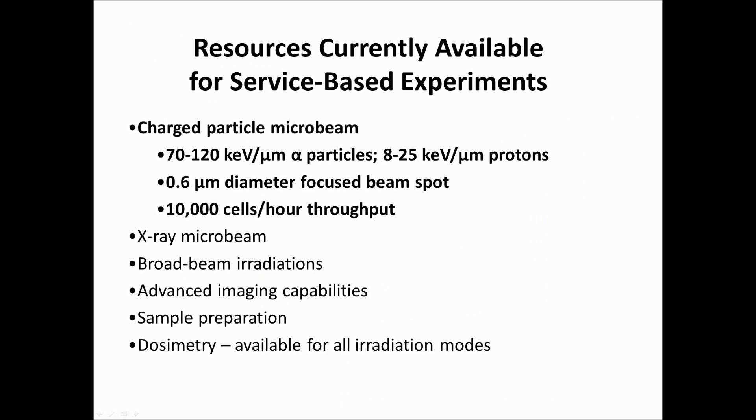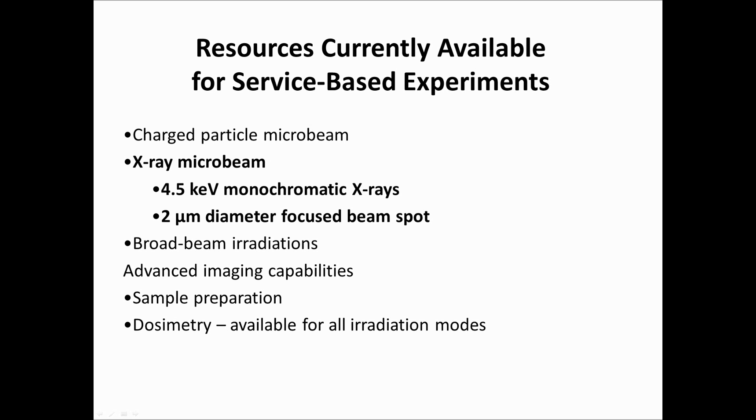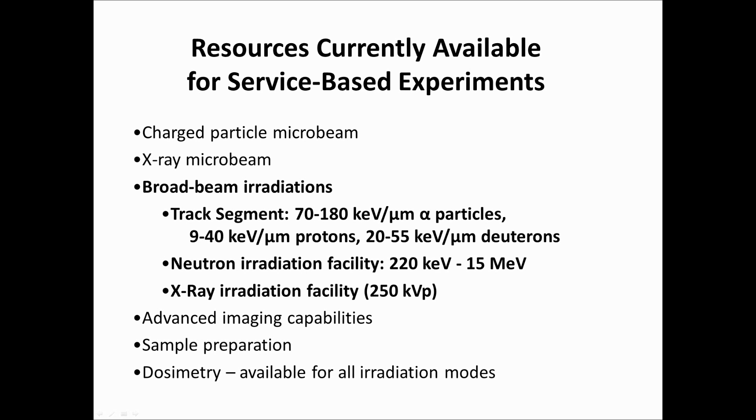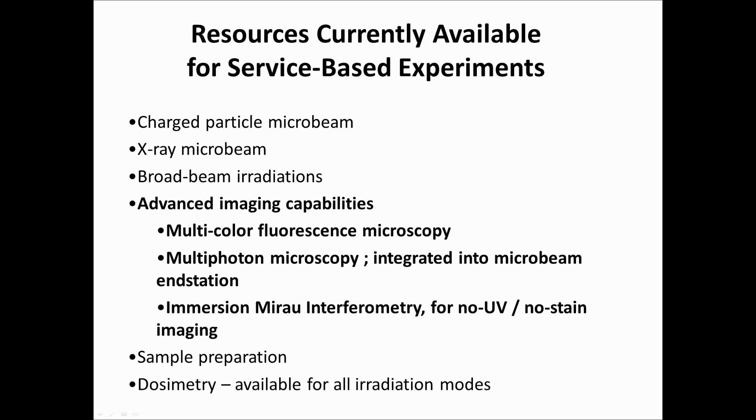These are things that we currently have at RARAP. The charge particle microbeam, alpha particles of 70 to 120 keV per micron or 8 to 25 keV per micron protons. 0.6 micron diameter spot, 10,000 cells per hour. We have the X-ray microbeam with monochromatic X-rays, 4.5 kV, 2 micrometer diameter spot. Broad beam radiations track segment, alpha particles, protons and deuterons.